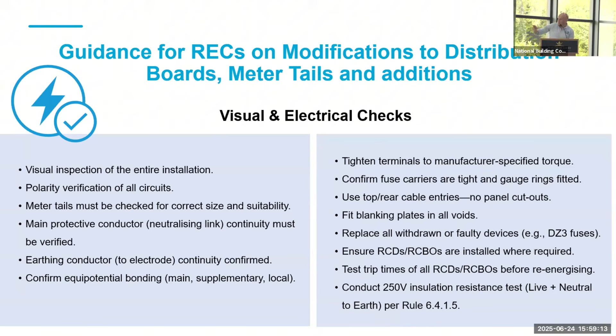Your lights will still work, your fuse won't blow, but the problem with that is if your mains neutral drops out, your whole house's return path will go on that little small cable, and eventually that cable will burn out. So again, this is a very important test that we get RECs to undertake. So should any of the above or hazards identified on the substandard, the registered electrical contractor shall either rectify the problem or issue a notice of potential hazard, which is a form, again, that we provide to the contractors.